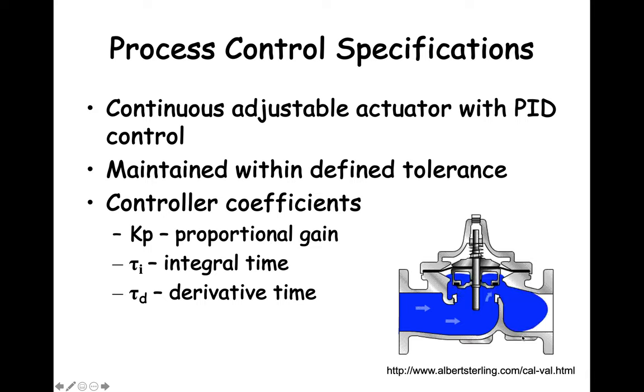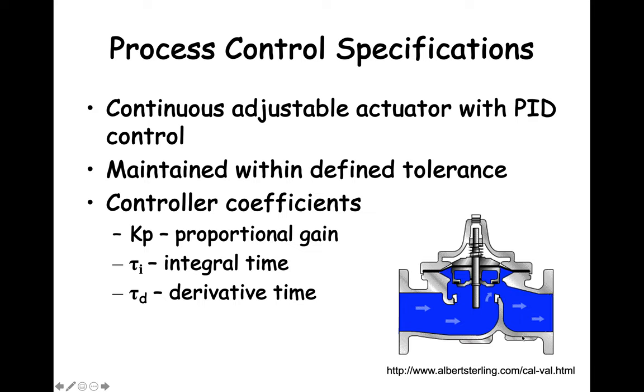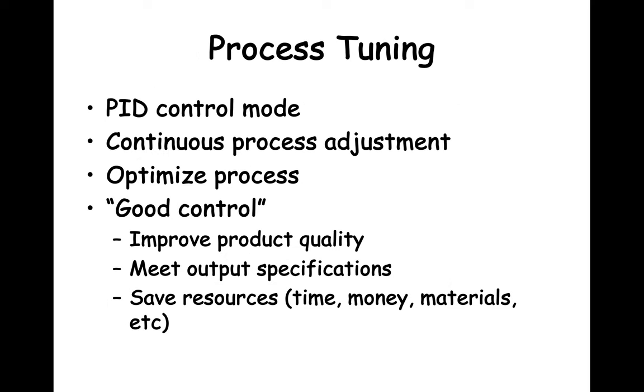In addition to maintaining the precise output within some specified tolerance, good control is assessed by how the system responds to a step change in either the setpoint or a process input. The size of the step change will depend on the expected setpoint or load changes the process would be expected to experience. Process tuning is used with PID control and it's an effort to find the values of Kp, tau i, and tau d to calculate the actuator process adjustment needed to get the process output within desired tolerances. The actuator must be continuously adjustable, and you are trying to find the best settings of Kp, tau i, and tau d to optimize the process and get good control.